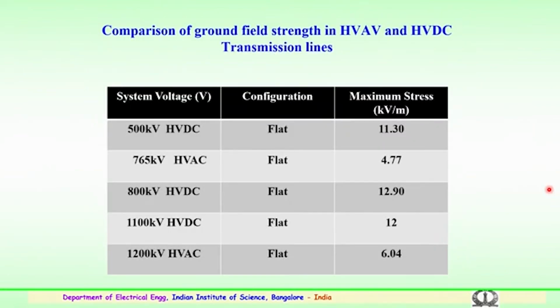So, again a comparison of the ground field strength for high voltage AC and HVDC. This gives the summary of the system details, from 500 kV DC, 765 AC up to 1200 kV AC, both for AC and DC. For various towers, the flat type of towers, what was the maximum stress obtained, in kV per meter, as shown here.